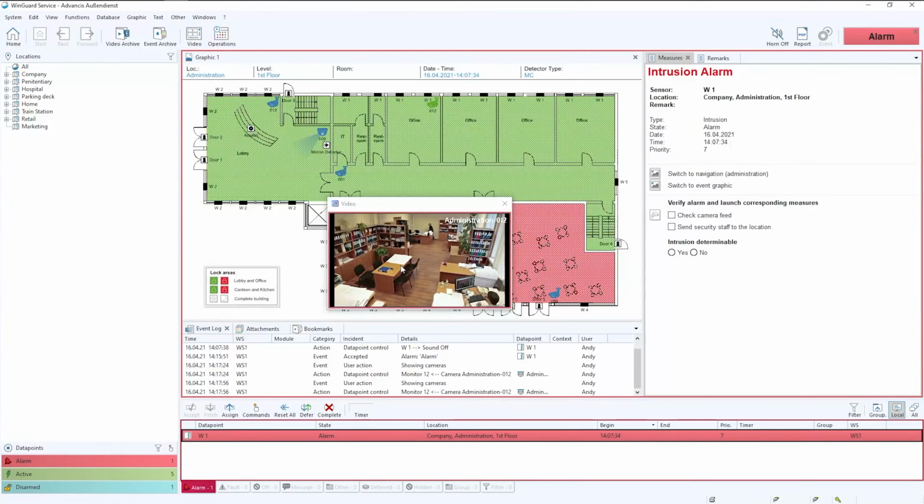So we're going to call the police, again using a SIP interface would be possible. We can call reinforcements via the radio interface, and the next action is for us to lock the doors down. So this may be locking down areas within the building to ensure that the intruders can go no further. So by clicking this button, we initiate a series of events that you'll see down in the event log, which has now said door 2 block. That means that door 2 has now been locked via the access control system via the integrations.